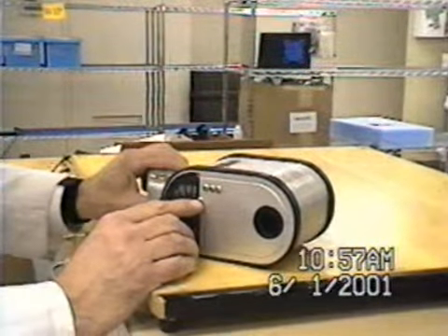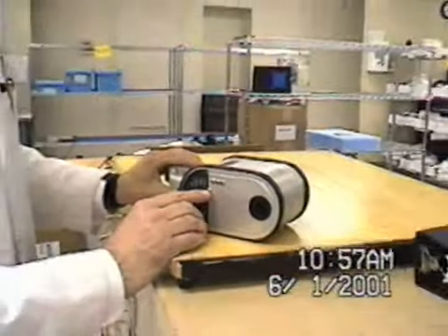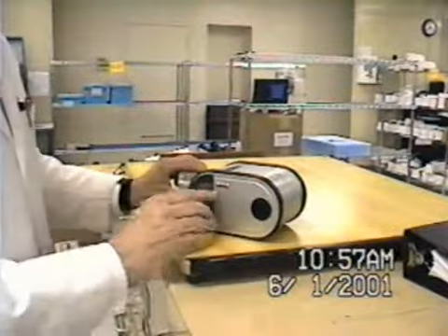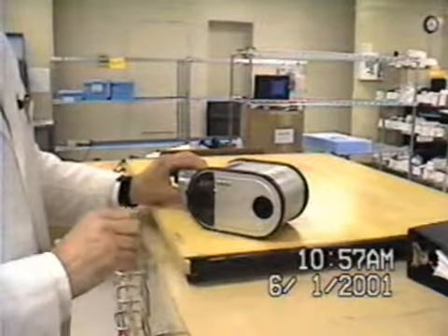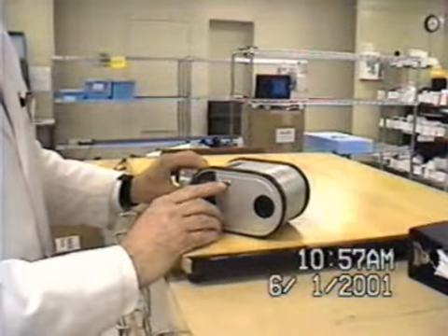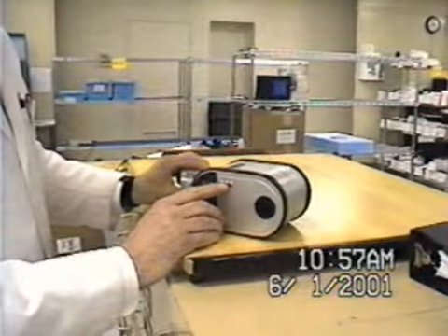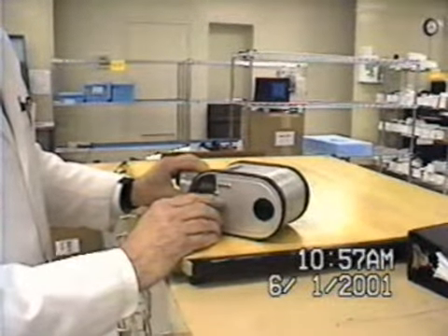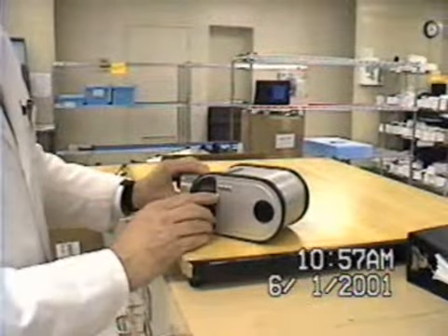We have to have that recalibrated. The reason why I'm not 100% sure is because dust gets on that calibrating surface and changes emissivity. So theoretically it should be 5 when it's brand new, but I think this has been oxidized and this is closer to 10. You have to have it calibrated.